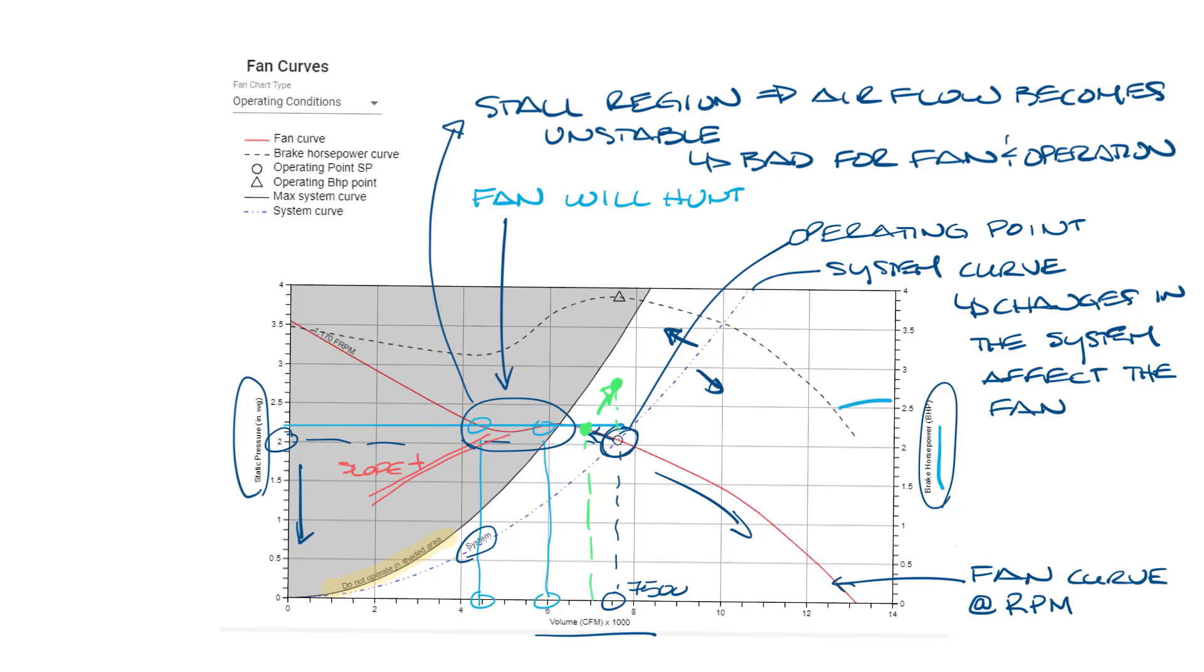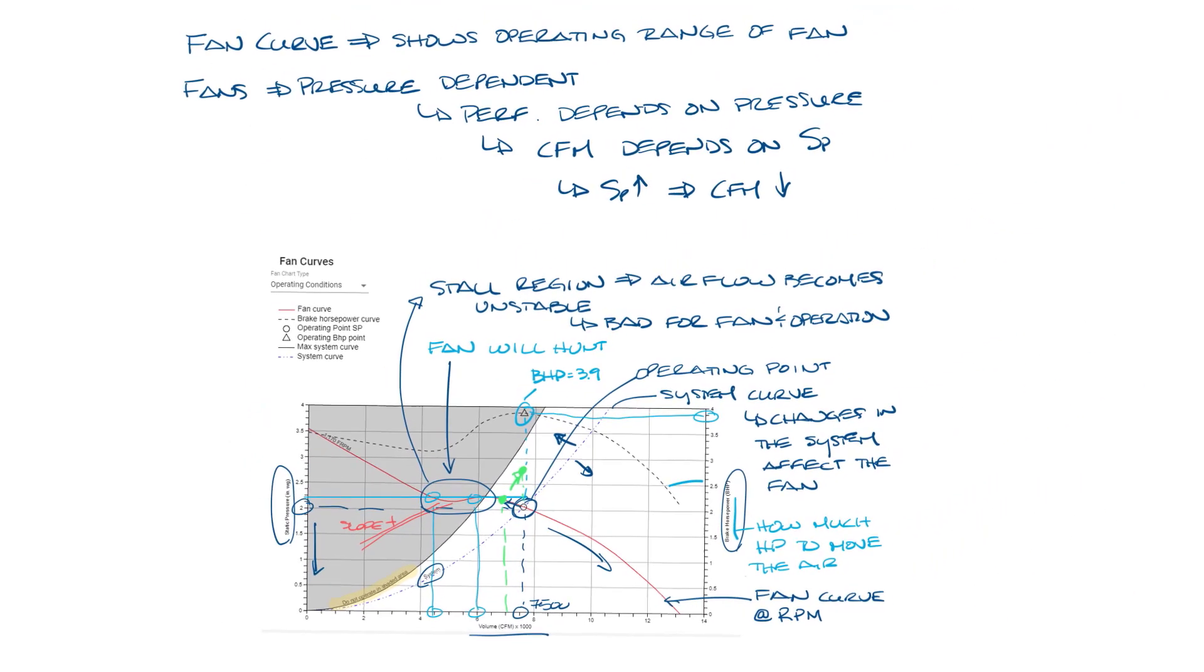Next, we have this dashed line up here. This is the brake horsepower curve. This shows how much power it'll take to move the air. To find this point, you basically draw a line straight up or down from the operating point. So this shows that it'll take about 3.9 horsepower to operate the fan in these conditions. Let's bring it all back on the screen.